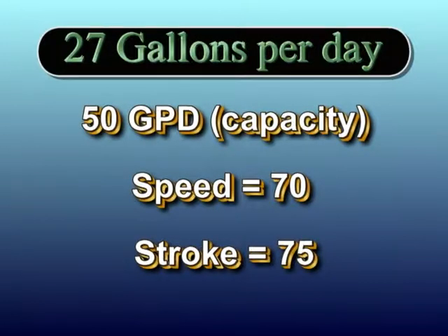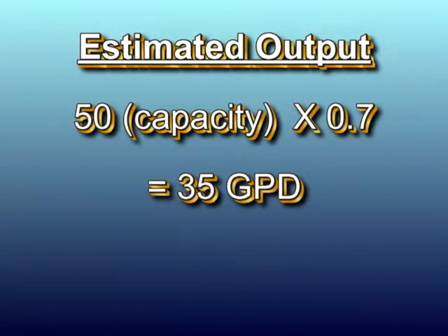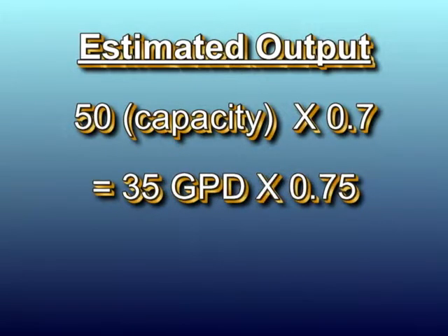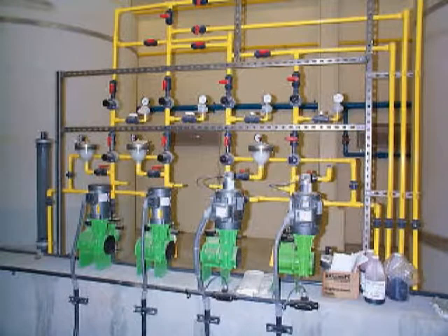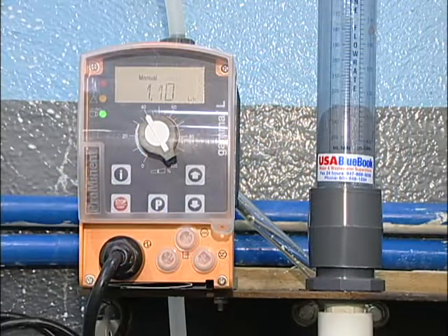...the pump should be delivering about 27 gallons a day. To get this estimate, the maximum output of 50 gallons per day is multiplied by the speed setting of 0.70, yielding 35 gallons per day, then by the stroke setting of 0.75, which gives about 27 gallons per day. Regardless of whether the manufacturer suggests this method, the best way to determine the efficiency of a pump is to do a pump calibration.